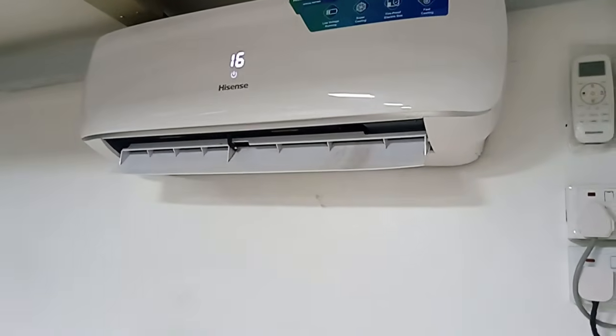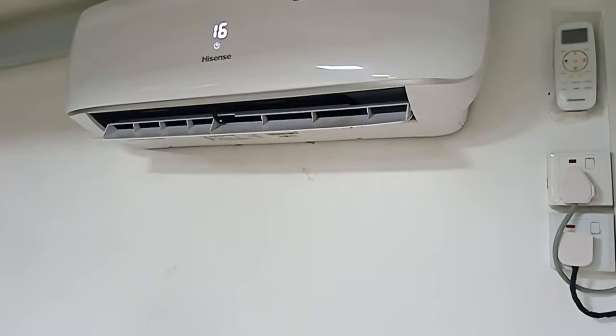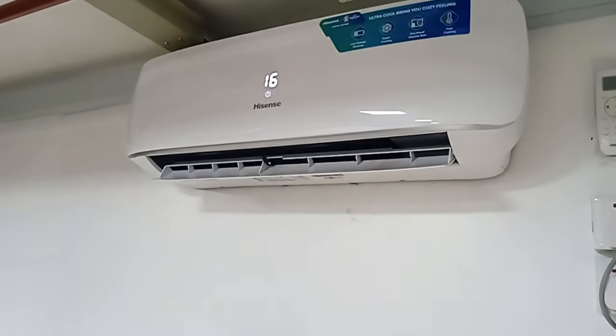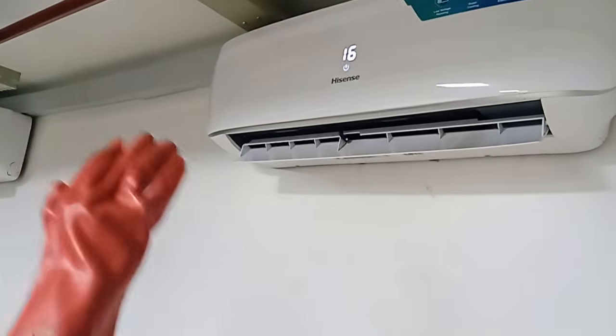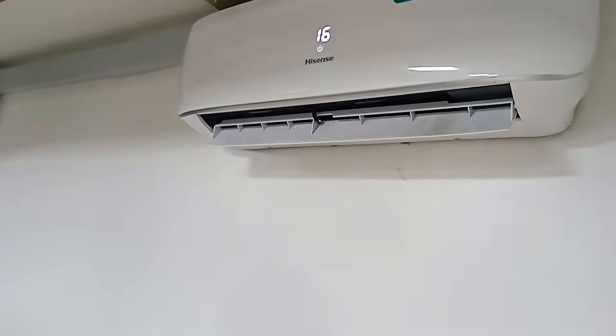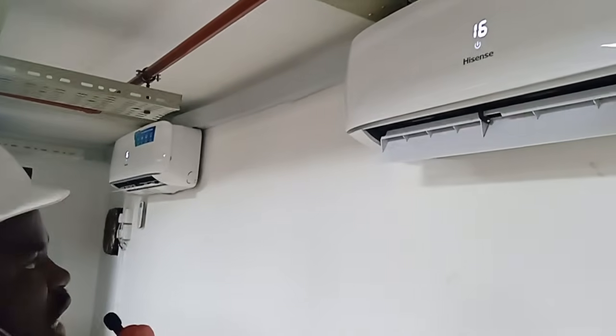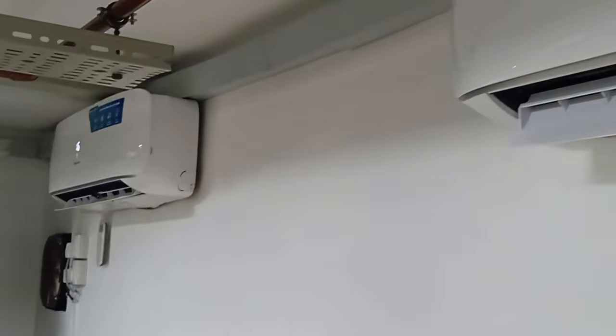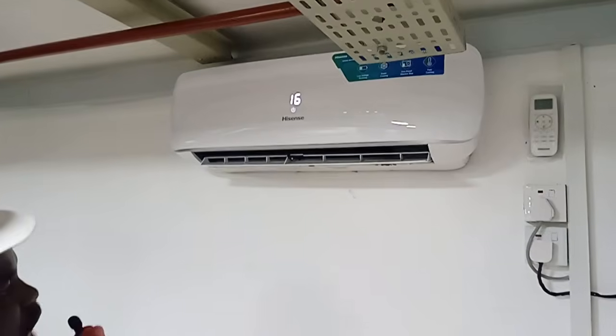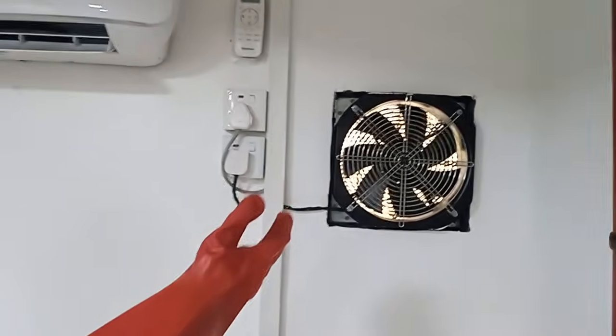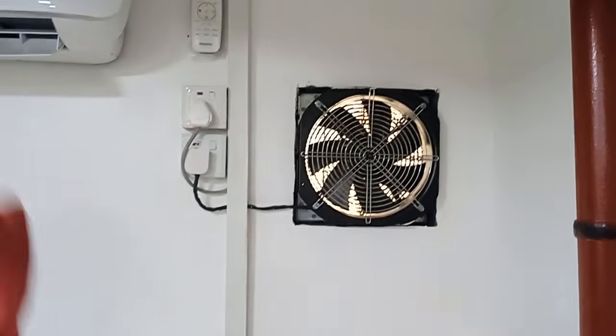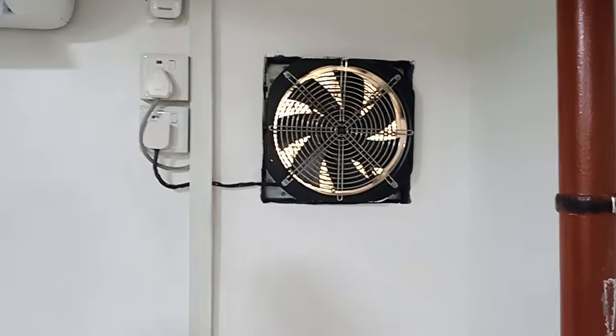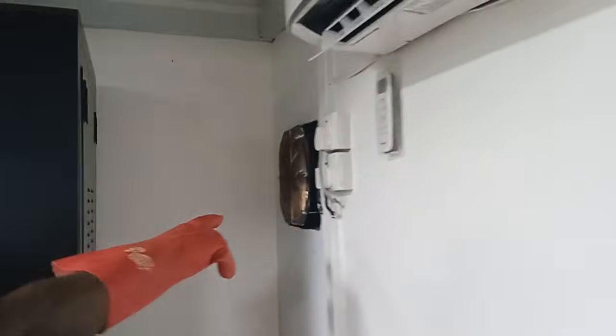In this power station, we have two AC units that make sure that the inverter and the batteries operate at their optimal temperature. We have these cooling units that help to bring down the temperature. This inverter, like I said earlier, is an industrial inverter. During its operation, it emits a whole lot of heat. Then also we have the heat extractor. The heat extractor helps to take away the heat inside this inverter room to the outside world. And also we have another heat extractor right here. It helps to take away heat outside.